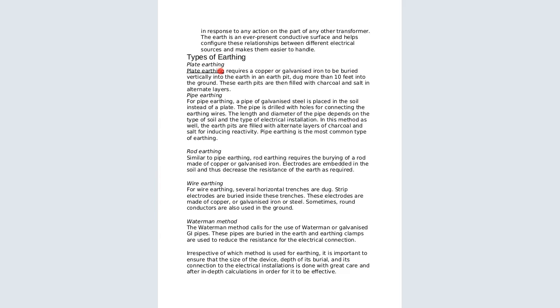So the types of earthing that we have, number one, is called plate earthing. What is plate earthing? Plate earthing requires a copper or galvanized iron plate. Later on, we are going to look at the pictures and the diagrams of how they look. So plate earthing requires a copper or galvanized iron plate to be buried vertically into the earth in an earth pit, dug more than 10 feet into the ground. So these earth pits are then filled with charcoal and salt in alternate layers.